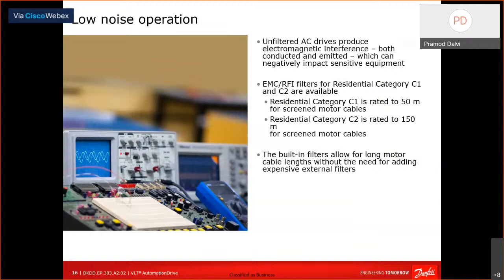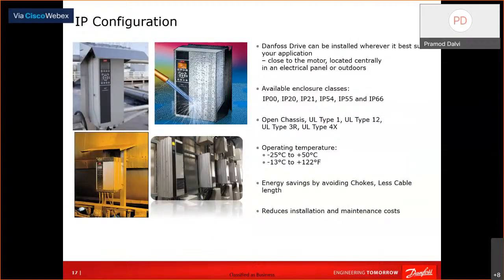On low noise operation, the EMC filters and RFI filters are built into this VFD. For longer cable lengths, more than 150 meters or beyond that, we have dedicated RFI filters built in. This is where I think we are more successful, in the long motor scenario, when the motor and VFD cables are long, with filters built in. Unfiltered AC drives will produce electromagnetic interference, which will have a negative impact on sensitive equipment.